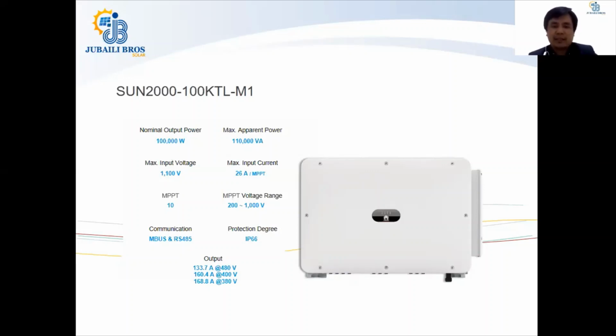Maximum input current is 26 ampere per MPPT. Now Huawei has increased the MPPT current compared with the previous range of inverters, from 12 to 60. You can see that those were made with 20 ampere per MPPT. But Huawei has increased the MPPT current and the short circuit current with the new range of Huawei inverters in order to make it adaptable to the newer and higher efficiency solar PV modules, especially the bifacial, because the current has been increased with the new range of solar PV modules.